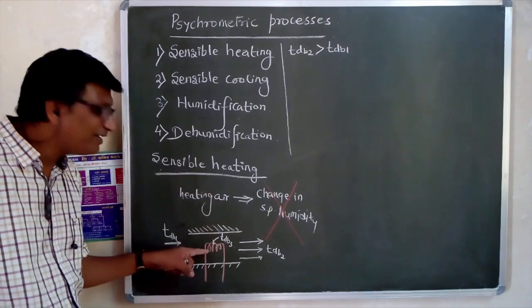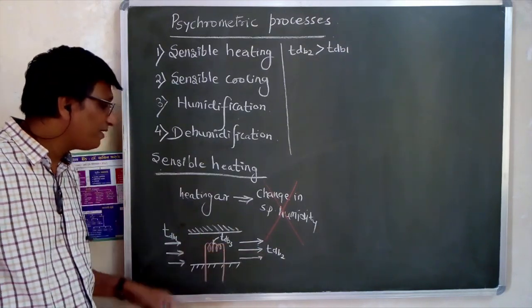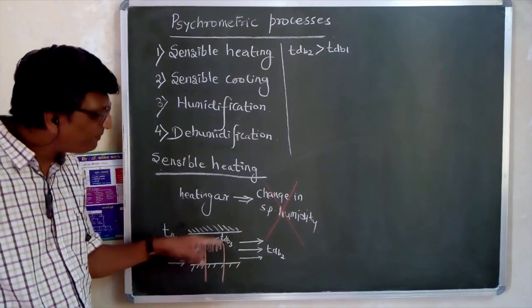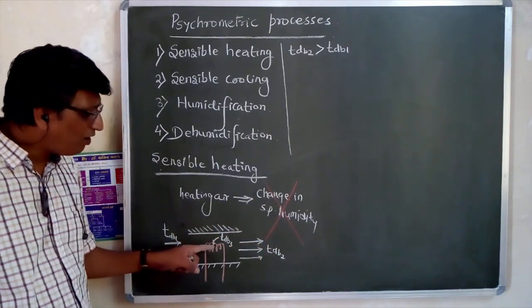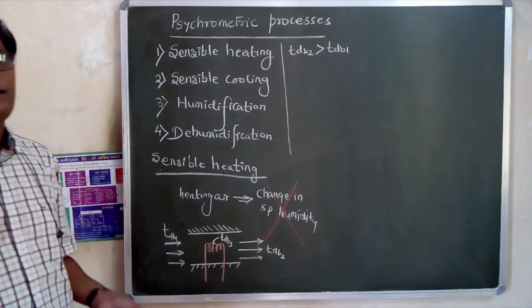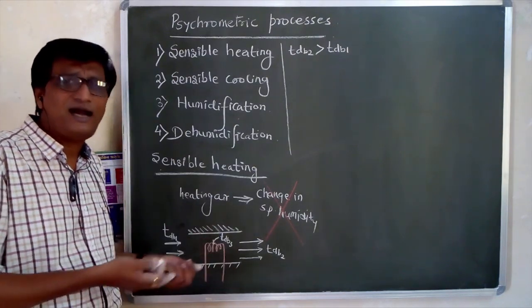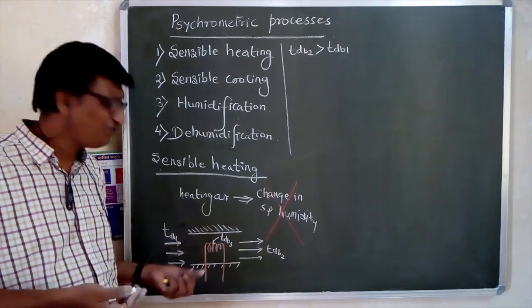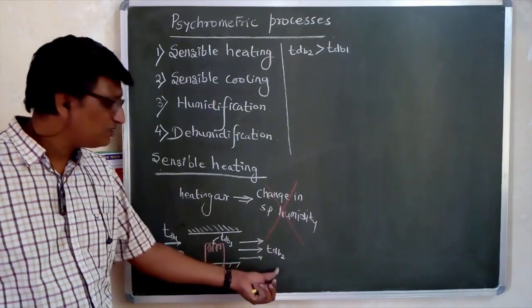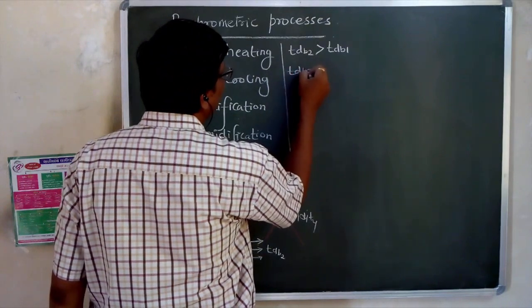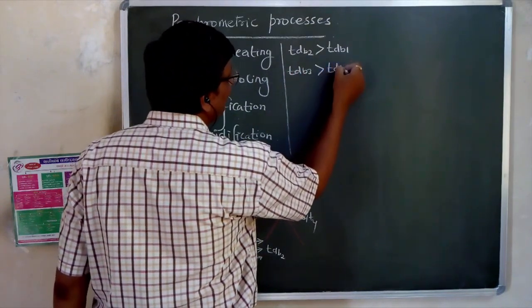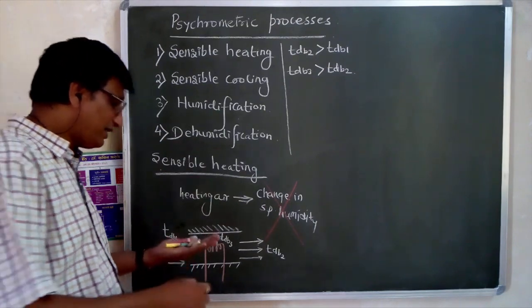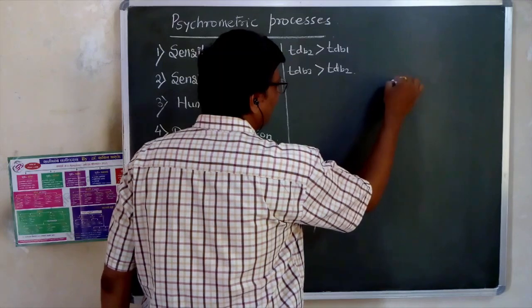One more interesting thing is that the coil temperature is more than the outlet air temperature. Why? If the efficiency of heat transfer is 100%, then the air temperature equals the coil temperature — whatever air passes through the coil takes 100% of the heat and reaches TdB3. But no process is 100% efficient, so the coil temperature is more than the outlet temperature. That means TdB3 is greater than TdB2. This is the sensible heating process. Now let us see that process on the psychrometric chart.